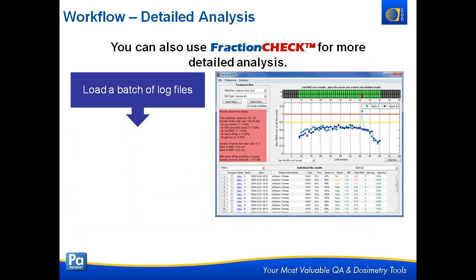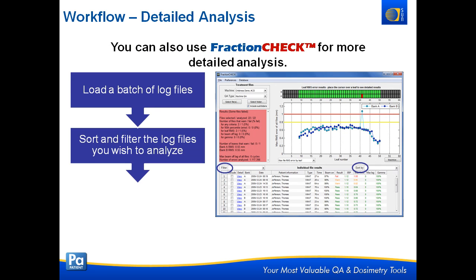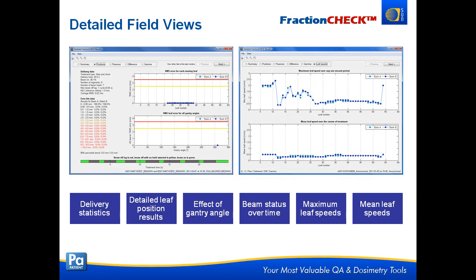You can also do a lot more detailed analysis. You can load a batch of log files, filter and sort, and then select different desired graphs and view detailed results for individual fields. These detailed field views show delivery statistics, leaf position results, the effect of gantry angle, beam status over time, and maximum and mean leaf speed — extremely advanced analysis of every field you're delivering.